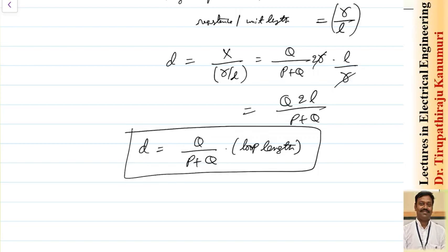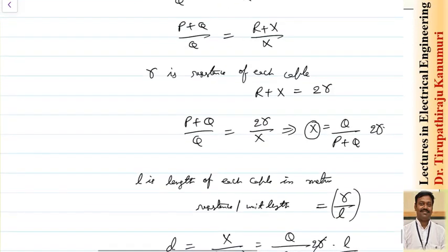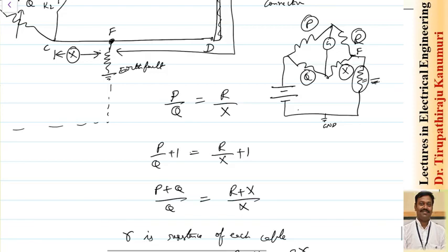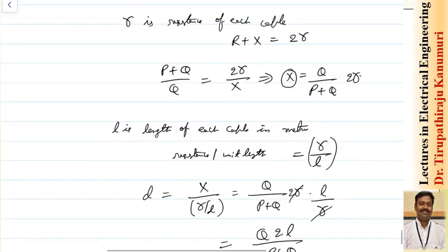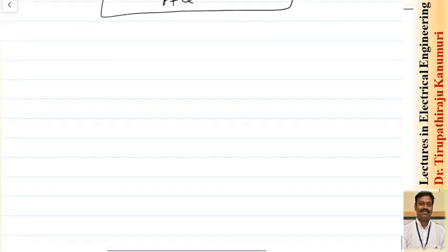This measurement method is most commonly used because the fault resistance is not considered within the Wheatstone bridge — it does not affect the bridge balance. So it measures the exact length of the cable where the fault is happening; that is a major advantage. However, since fault resistance is included in the battery circuit, it affects how much current is supplied by the battery, making the bridge less sensitive. You may need to vary the resistors more to achieve balance, but under balance conditions the value will be accurate.